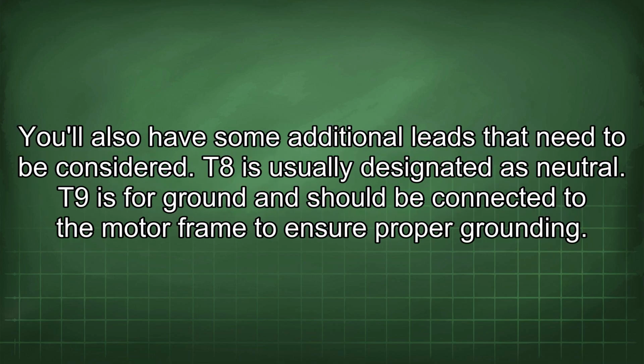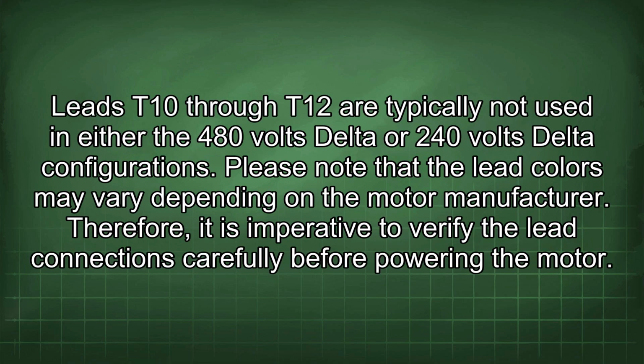You'll also have some additional leads that need to be considered. T8 is usually designated as neutral. T9 is for ground and should be connected to the motor frame to ensure proper grounding. Leads T10 through T12 are typically not used in either the 480 volts delta or 240 volts delta configurations.